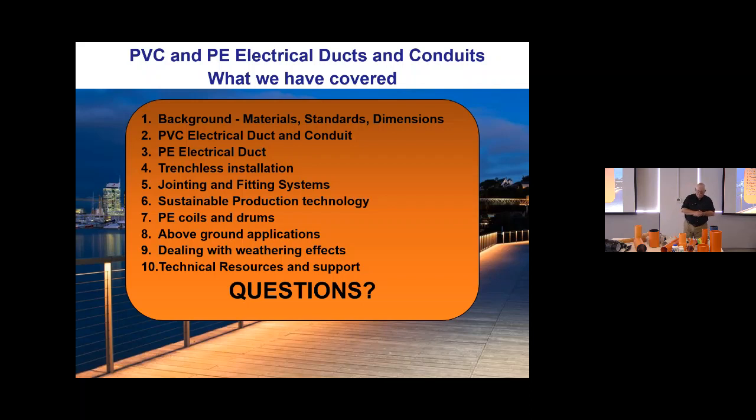What's your experience? At that kind of temperature, sort of in the 60 to 70 range, no. The extrusion temperature, or the temperature at which polyethylene melts, is typically about 195 through to about 210 degrees centigrade, and for PVC, about 180 to 190 degrees centigrade. So that's the melting point of the material. But these materials go through a softening phase below that.